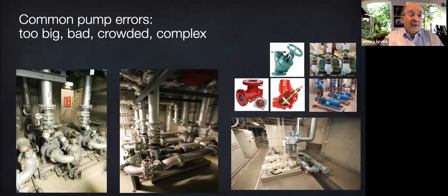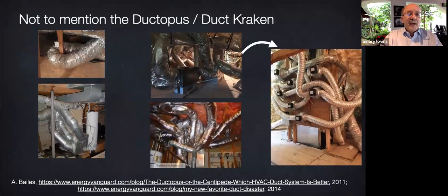On the discharge side, these triple duty valves, check and throttling and shutoff valves, are another artifact that seems to save capital costs, but actually needs more energy and bigger pumps, costing more than if you use best layout practice. Just pipe properly and design those things out. Duct systems can present the same graphic and disturbing images of dreadful layouts with high friction and thus unnecessarily big, costly, noisy, inefficient fans and blowers. Physicist Dr. Allison Bailes collected these gems, and somebody commented, "I would use one of those ducts to strangle the designer rather than the installer."